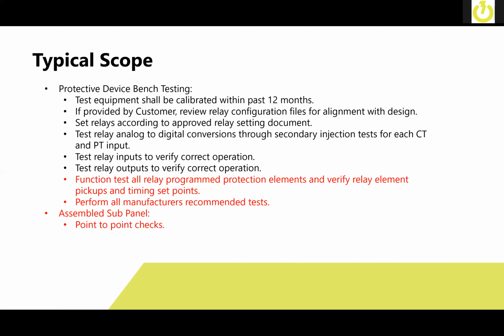If provided by the customer, review the configuration files for alignment with the design. For instance, whenever we get relay settings from somebody, a common issue is on transformers, where you have a phase shift from the primary to the secondary. If the relay settings don't properly match that phase shift, you could have inadvertent operation whenever it gets started up. The relays are set according to the approved relay settings document.